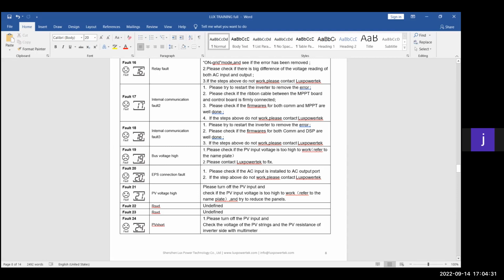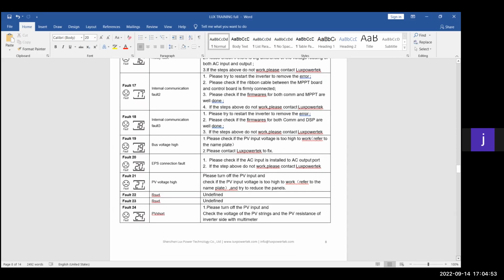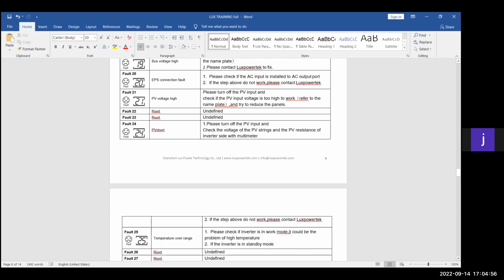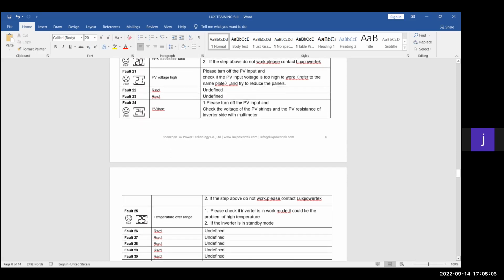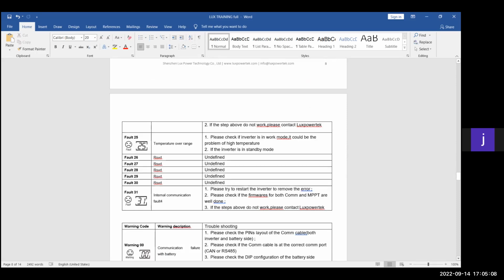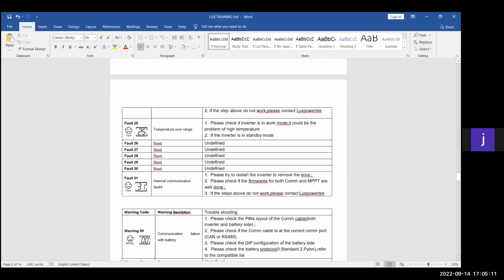Let's say the battery should reach 56 volts, but it stops at 53 or stops at 55.3 or 55 volts, and then the BMS will completely cut off the charge, and then the voltage between the inverter and the battery will go higher than the BMS cable tells the inverter it is, and then it gives you this error that happens on number 19. So we have a few systems. After a lot of the updates that engineers have done on the logic of the inverters, it improves that voltage one, but it's not an error that happens a lot. We just have a few systems where it happens after the updates. 99% of them are completely sorted out.